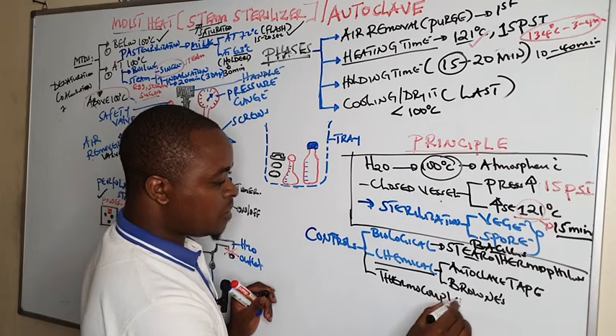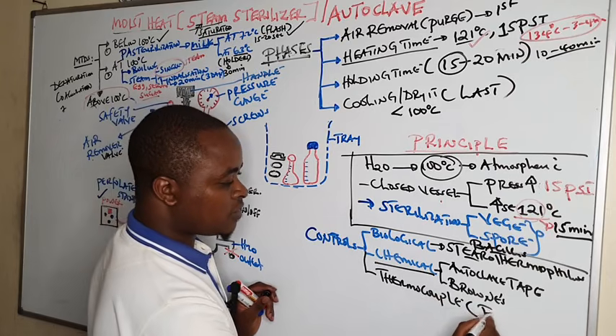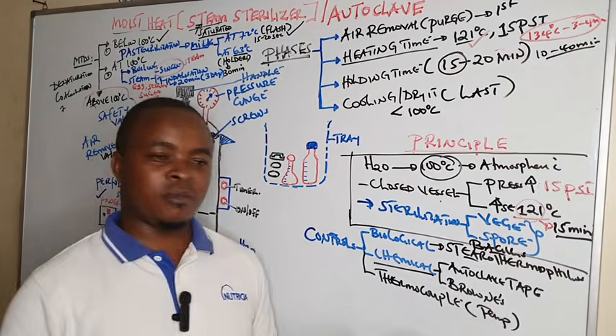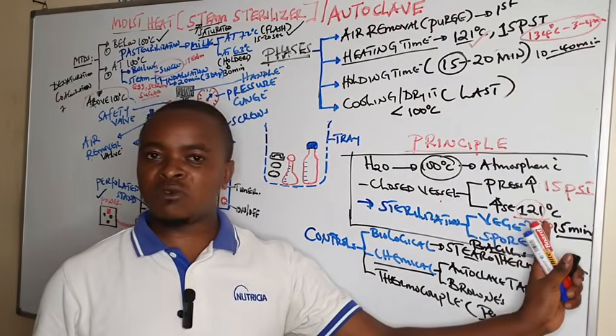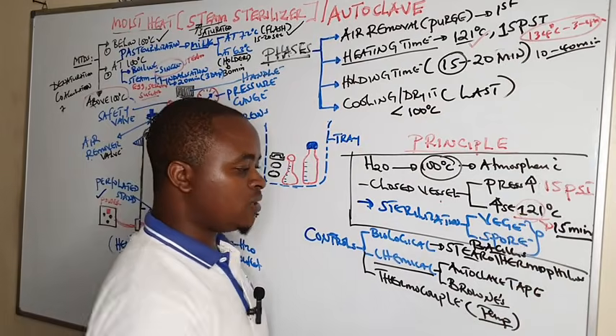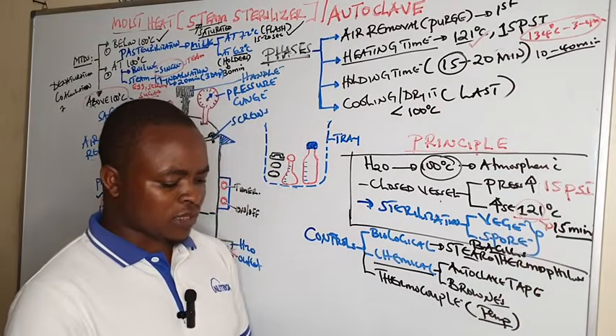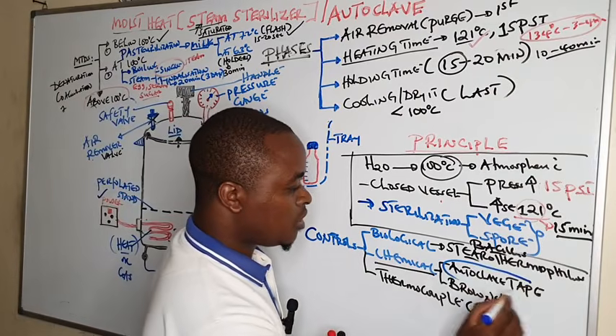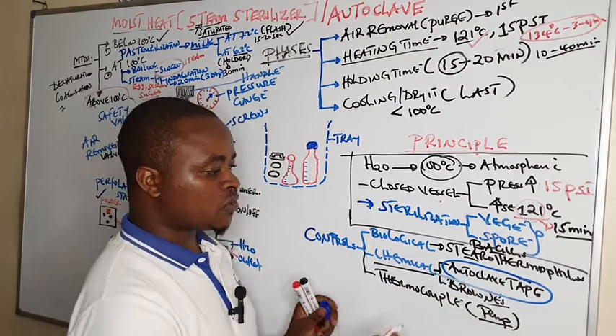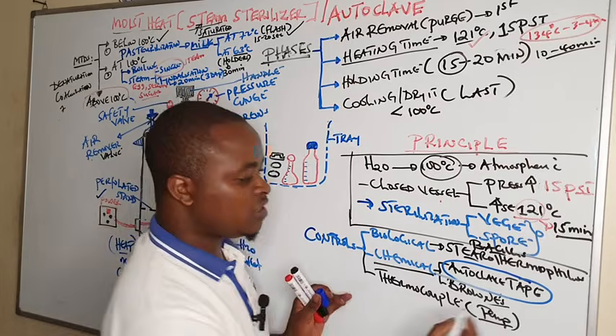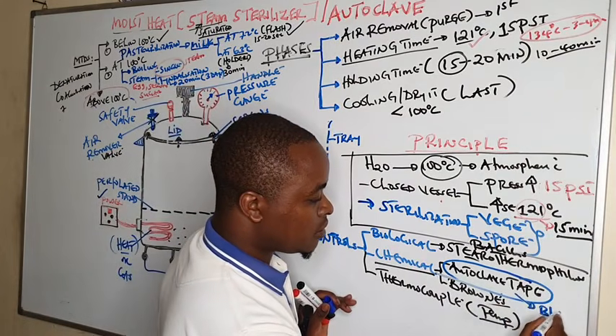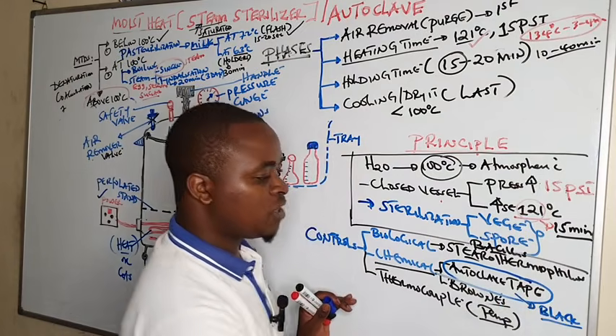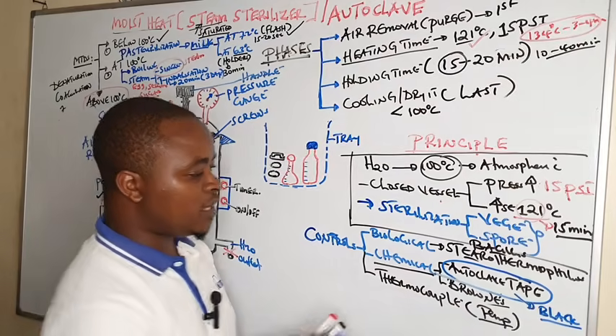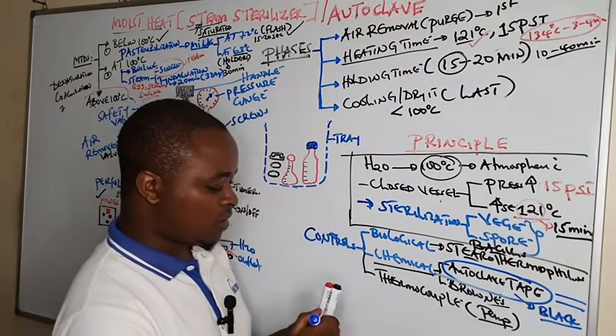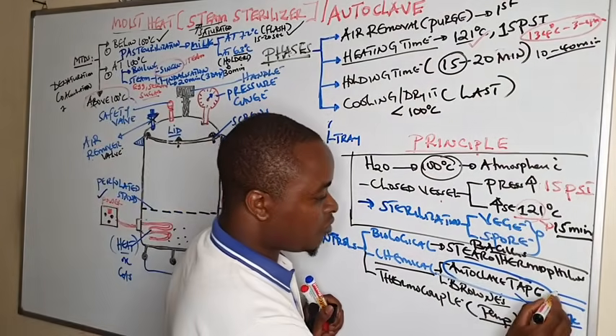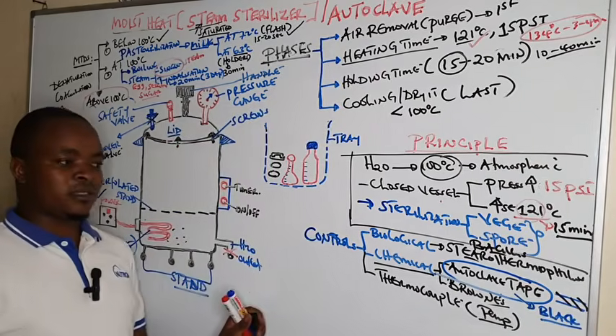These thermocouples are inbuilt, and they help us to monitor temperature. It is an inbuilt thermometer that monitors the temperature to make sure it is at 121. Then also Browne's control can be used, but the most commonly used control is the autoclave tape. It is always colorless, but when sterilization is achieved, it turns black. Some diagonal strips which are black in color are formed. When this tape is used, after sterilization is achieved, it forms black diagonal lines.